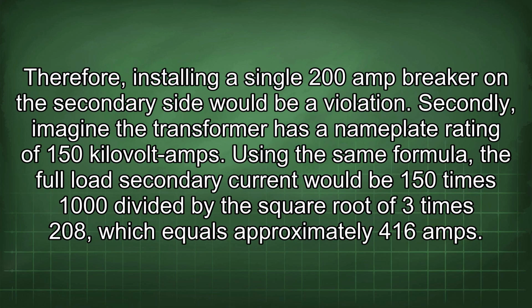Therefore, installing a single 200 amp breaker on the secondary side would be a violation. Secondly, imagine the transformer has a nameplate rating of 150 kilovolt amps. Using the same formula, the full load secondary current would be 150 times 1000 divided by the square root of 3 times 208, which equals approximately 416 amps.